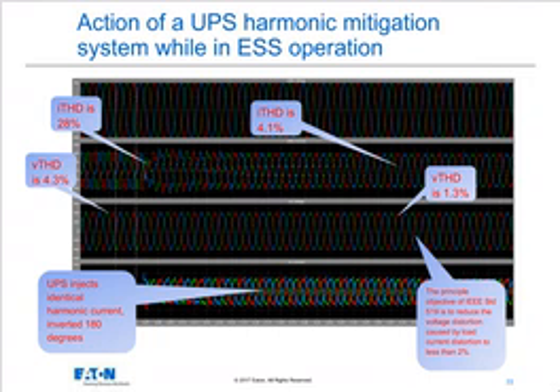This shows a rather busy picture of the way this harmonic reduction system works. It may be a little difficult to see on your screen because it is dark, but remember this presentation will be available to you to download for your own use. And if you have the time and you want to take a look at this information, what this is showing here is a distorted signal being reflected back through the UPS from a harmonic-rich load. The voltage distortion is unacceptable, as is the current distortion, as Dan explained. And when the action of the harmonic mitigation system takes effect, it only takes about 15 cycles or 1/4 of a second to bring that current and voltage distortion back into acceptable limits. So it's a very flexible and adaptable option that is available on some large UPS systems out in the field.